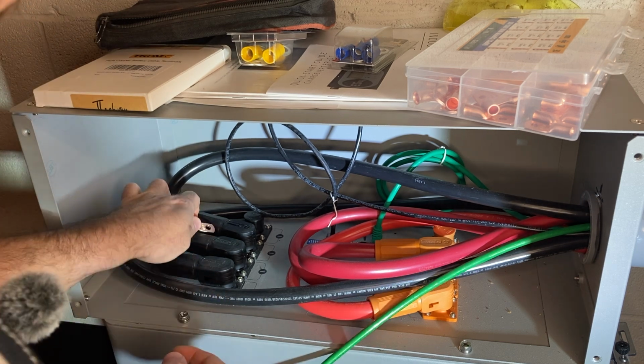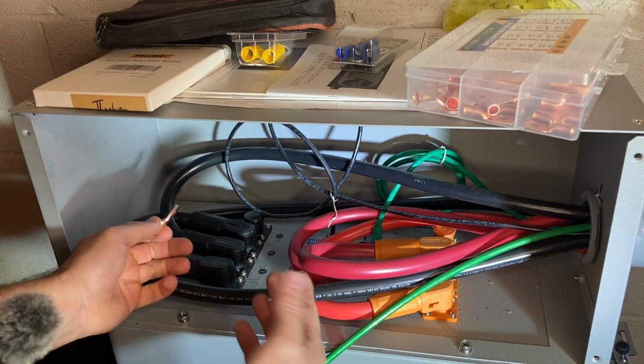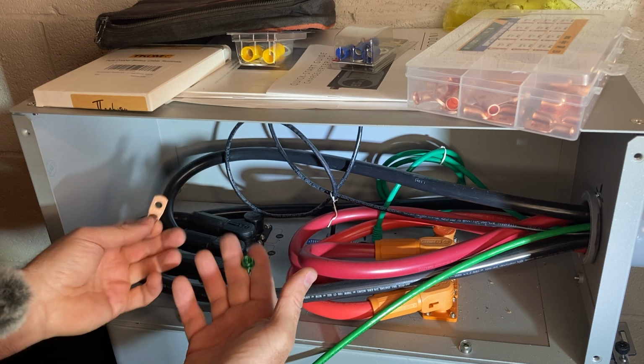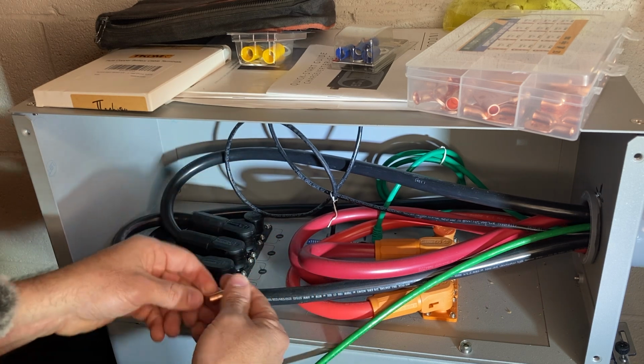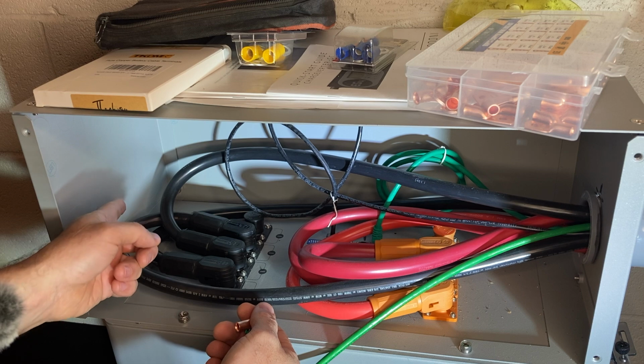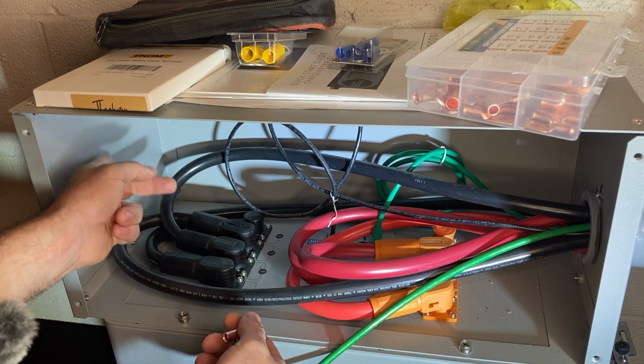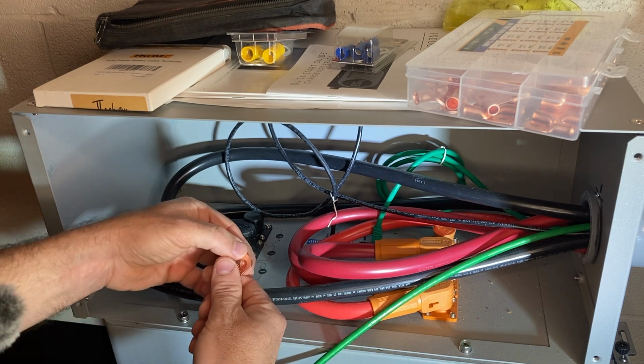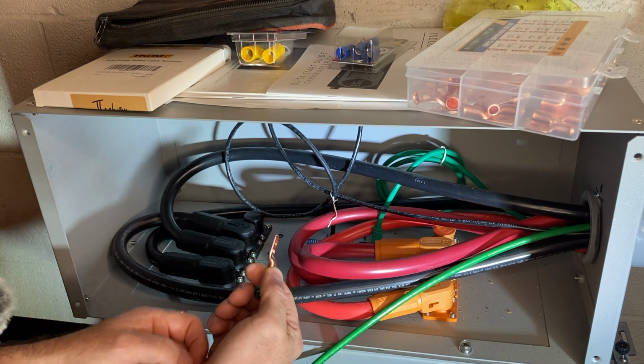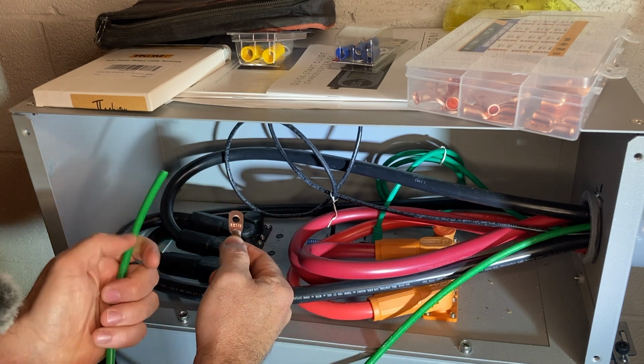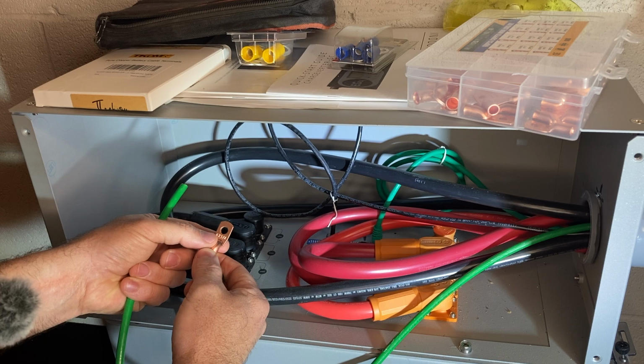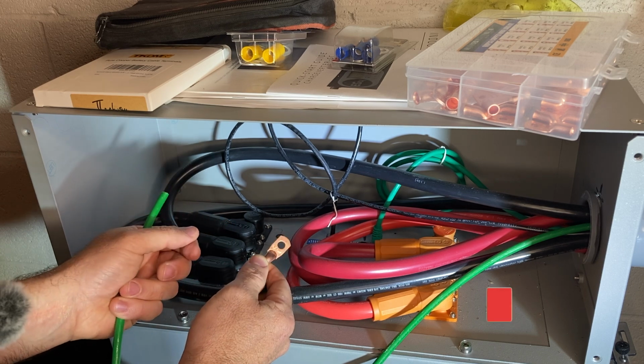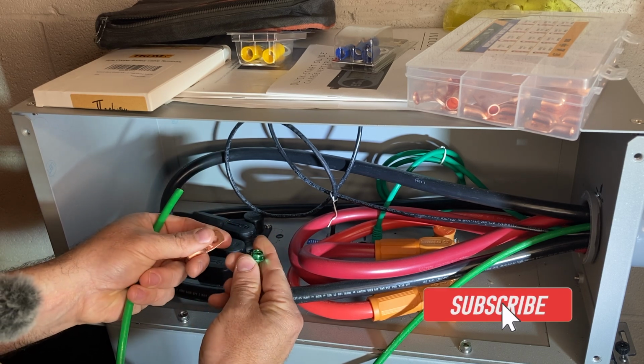We are sort of doubling up here. I don't think you can see because all these wires are in the way now. Probably should have done this originally, but it's already got that little jumper from this conduit box over to that lug. So we're doubling up some grounding lugs here. I don't really see an issue with it, but technically it could be a code issue. I don't know that you can double up terminals on one single ground screw.